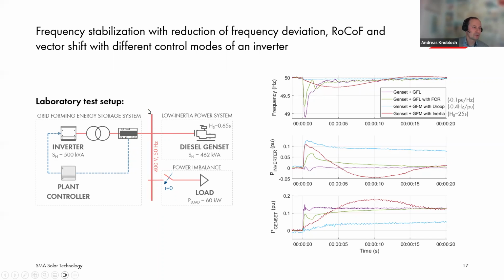On the other side, we have connected an inverter system to it via a transformer. This is a downrated Sunny Central storage inverter that we have operated in different control modes. The control modes were grid following control mode, so GFL. Then grid following control mode with frequency containment reserve, so primary frequency response, but in a grid following way. Then we operated the inverter in a grid forming mode with a droop control, and in grid forming mode with inertia control with the respective H constant. It's quite a high inertia constant, and the droop constant here is minus 0.4 Hertz per unit active power.